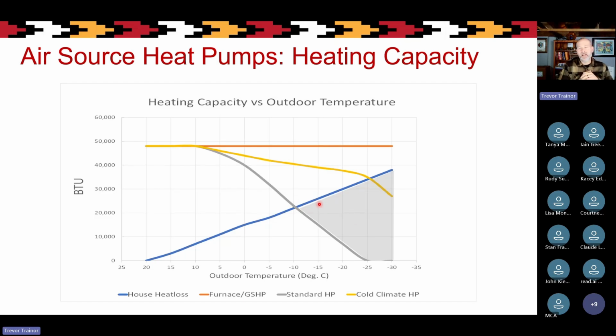Now, fortunately, we've developed cold climate heat pumps, which work a lot better and drop off at a much slower rate. In this example, they start to drop off in their capacity around the same temperature, but they really maintain their ability a lot longer. And in this example, we don't really cross over the heat loss until about minus 25. So after it gets colder than minus 25, we're still going to need a little bit of supplemental heat into our home to maintain 20 degrees Celsius. But it's obviously a much smaller amount because we're using this cold climate heat pump.